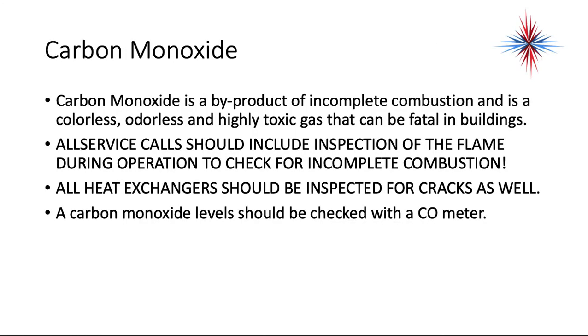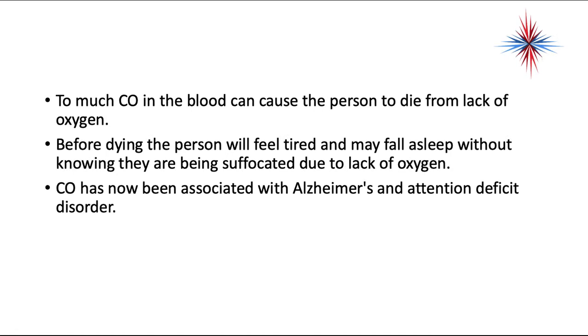Carbon monoxide is a byproduct of incomplete combustion and is a colorless, odorless, highly toxic gas that can be fatal in buildings. This is why incomplete combustion is so dangerous. All service calls should include an inspection of the flame during operation to check for incomplete combustion, and all heat exchangers should be inspected for cracks. Carbon monoxide levels should be checked with a carbon monoxide meter. Too much CO in the blood can cause a person to die from lack of oxygen. Before dying, the person will feel tired and may fall asleep without knowing they're being suffocated. CO has also been associated with Alzheimer's and attention deficit disorder.